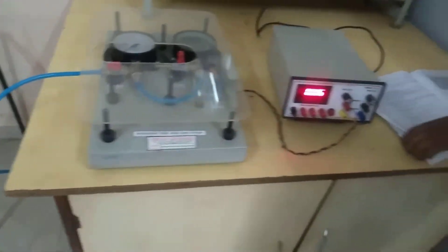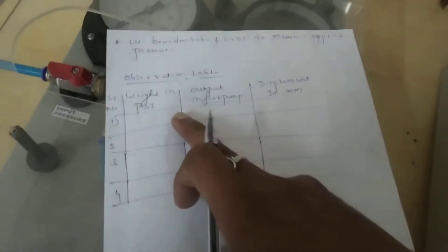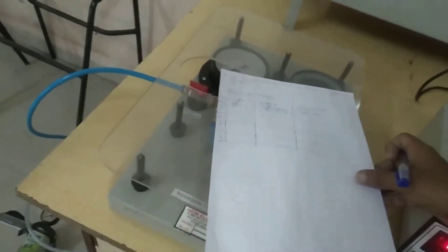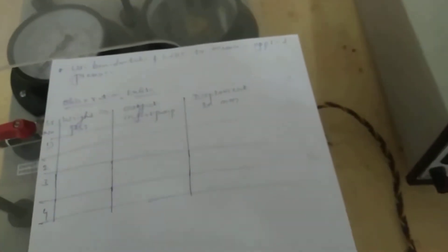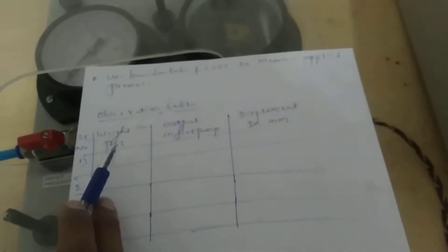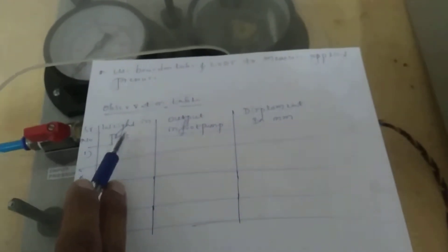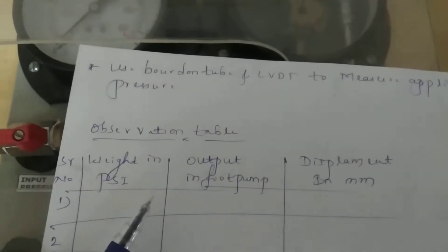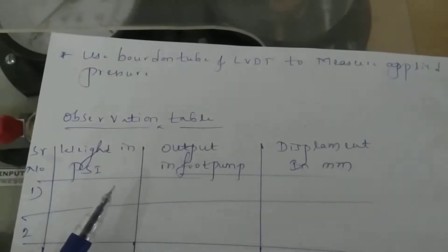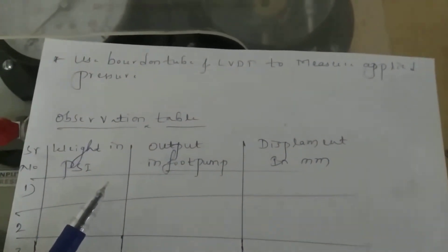So first we will take the reading. The output is from the foot pump, and the third column is displacement in mm. First I am going to apply the weight in PSI — that is pounds per square inch, or in terms of kg per centimeter square. The range you are getting from the pressure gauge is 0 to up to 150 PSI. So the first reading is 20 PSI. In the British system you measure in terms of PSI — pounds per square inch.